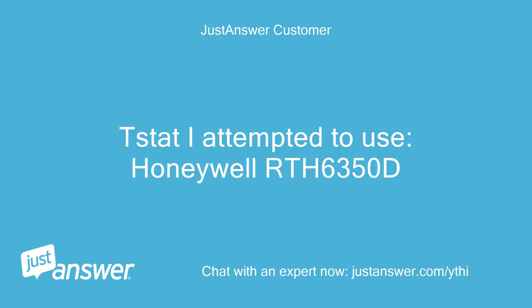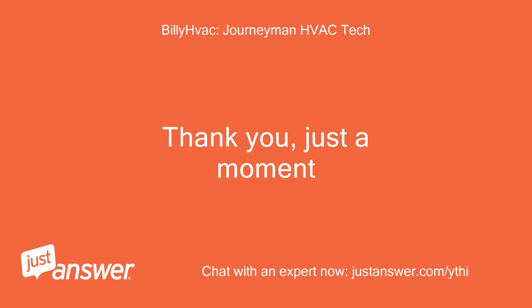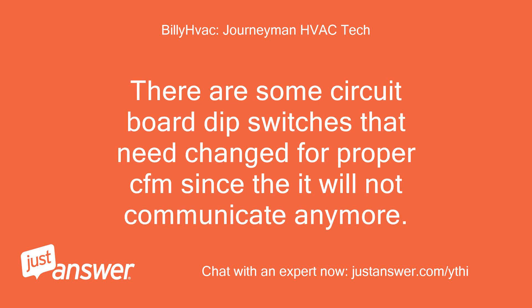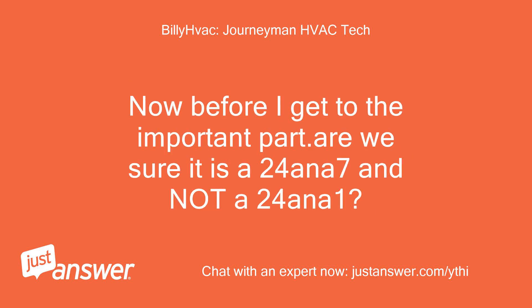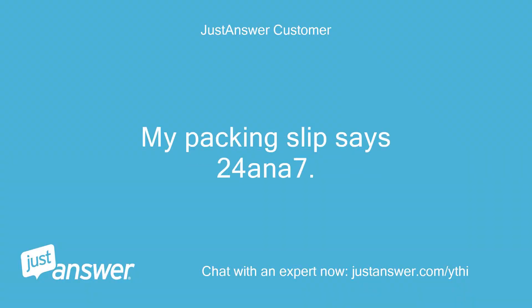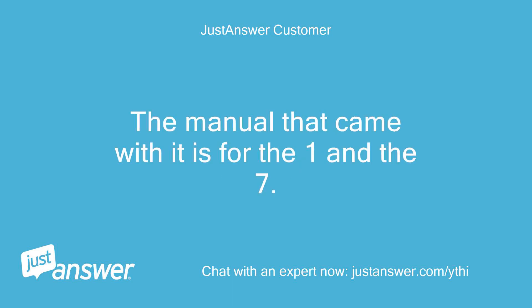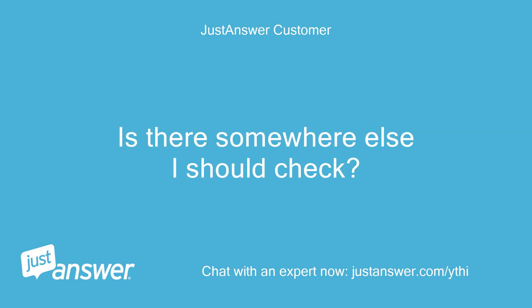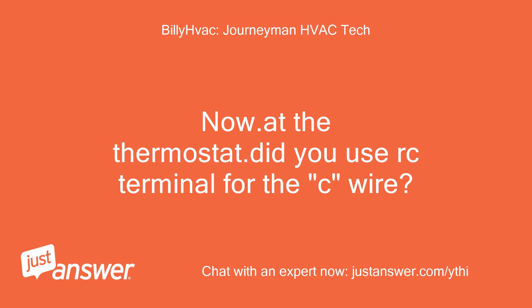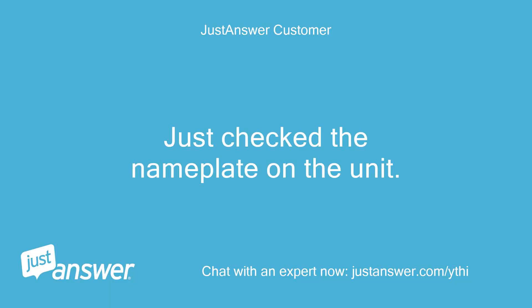I attempted to use a Honeywell RTH6350D thermostat. Just a moment. Okay, I see there are a few control changes when you revert to standard wiring. There are some circuit board dip switches that need to be changed for proper CFM since it will not communicate anymore. Are we sure it is a 24ANA 7 and not a 24ANA 1? I'm pretty sure — my packing slip says 24ANA 7. The manual that came with it is for both the 1 and the 7. Just check the nameplate on the unit. It's a 7.